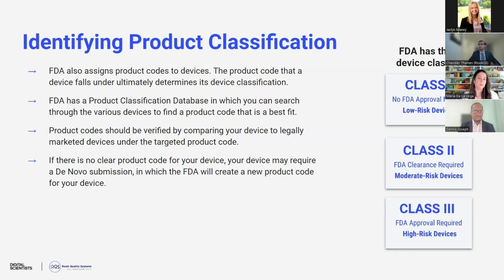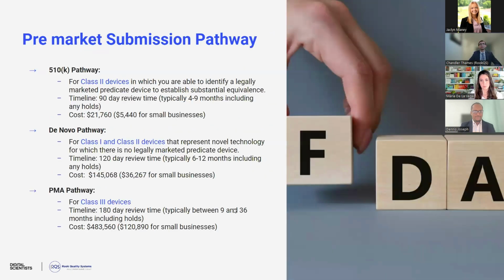Compare that to Class 3, which requires FDA approval. These are for high-risk devices, and the Class 3 device process is a bit more burdensome than the Class 2. Typically involves clinical studies or clinical trials. It involves FDA inspection of manufacturing facilities, and in general takes quite a bit more time. We can move to the next slide.